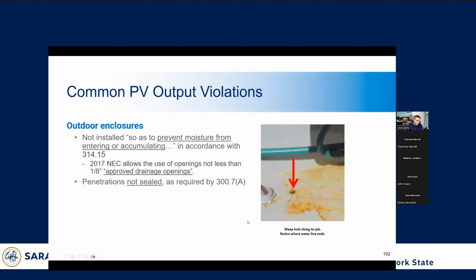Here you can see that the water line sort of ends right where the weep hole is. So this is showing that the rust line, that's where the water was. So it is showing that it's effectively draining the water. And obviously you want to keep in mind these should not be sealed, as the whole point is to keep them open to allow water to exit the enclosure.